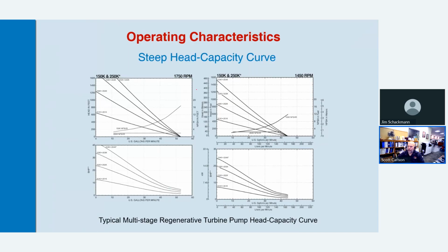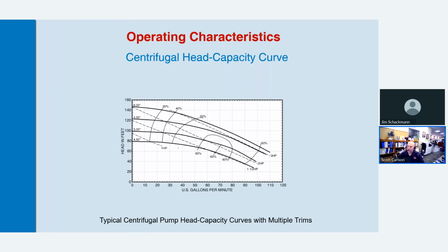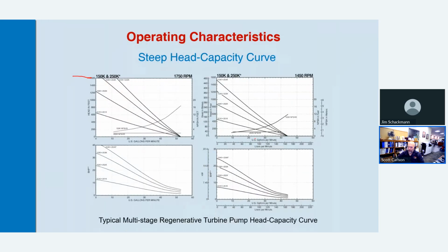An example for context is this multi-stage regen turbine. You can see the extreme amounts of pressure that it can achieve, but you'll also notice the horsepower is higher at higher pressures. When you compare that to a centrifugal pump, the centrifugal pump goes to a higher horsepower as the flow increases. So it's exactly the opposite of a centrifugal pump.